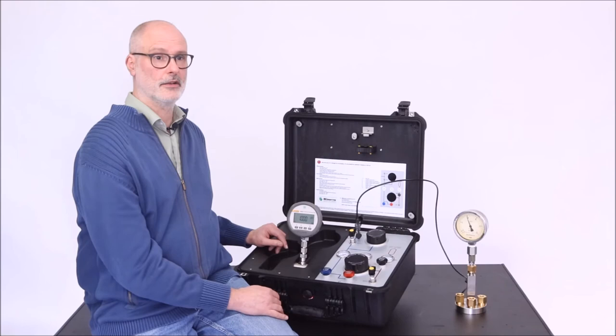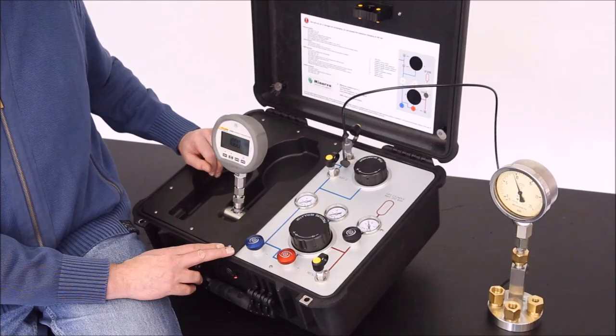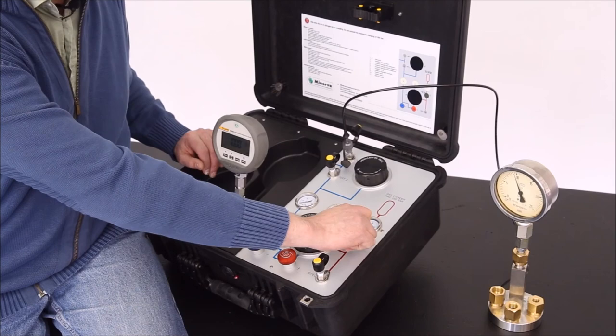At the end of the calibration, we want to make sure we leave the Minerva Portable High Pressure Case in a safe state. This means I'm going to close my bottles, isolate my bottles from the rest of the system, and I need to vent the system.